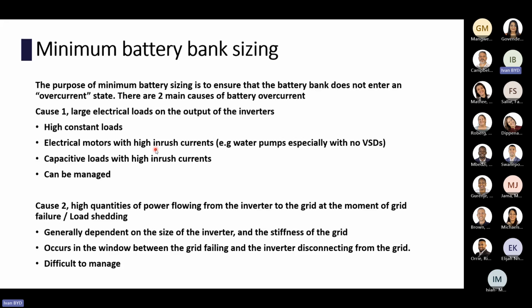But there's the other reason why you need a minimum battery bank, which is the interaction between the inverter and the grid. Because a lot of these inverters run in parallel with the grid. For example, when the inverter is running normally, your grid is 230 volts 50 hertz, your inverter is 230 volts 50 hertz, and they're both generating, and there's a relay in between.